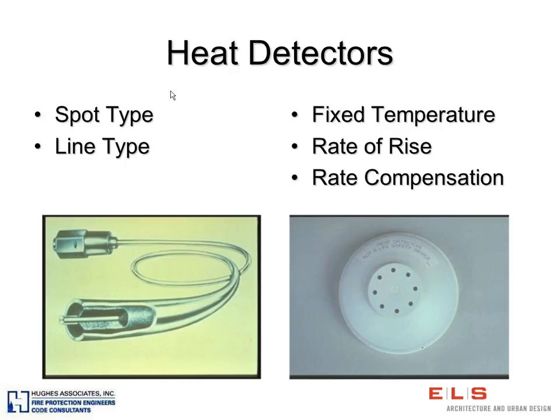For heat detectors, we have two general types of heat detectors. A spot type heat detector, just like this, it's typical. They look very similar to smoke detectors. It's just a dot on the wall, on the ceiling, and instead of there being a smoke detecting element, there is a heat detecting element. This particular heat detecting element is usually a rate compensation type. The rate compensation type is measuring the air temperature in relation to what it's been measuring in terms of the ambient air temperature. And we also have fixed temperature types of heat detectors, which just, when it gets to a certain temperature, say 165 degrees, that would trigger an alarm. An alarm would be triggered on a rate of rise detector if the temperature rises too quickly in a short amount of time. So there are different technologies associated with heat detectors.